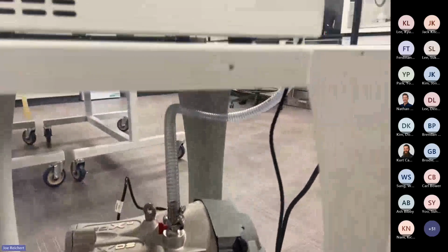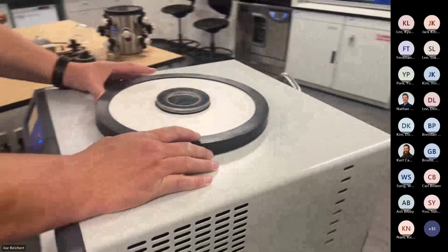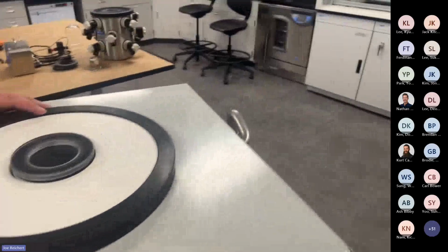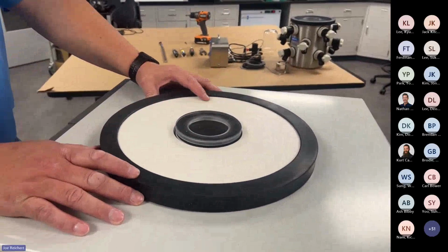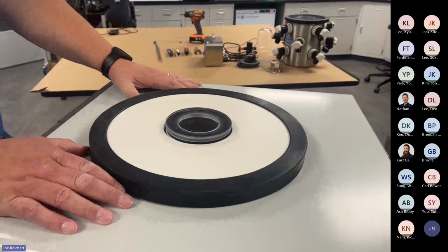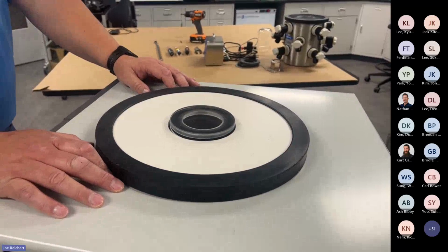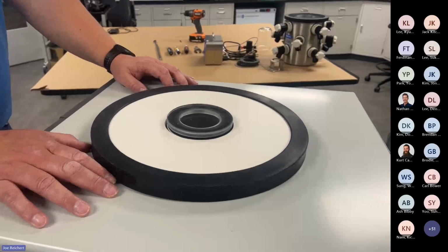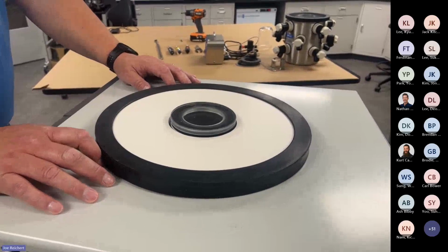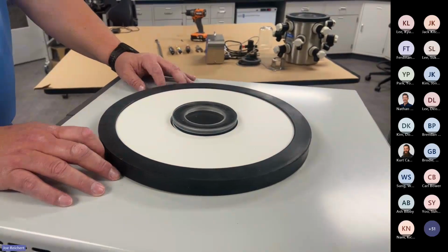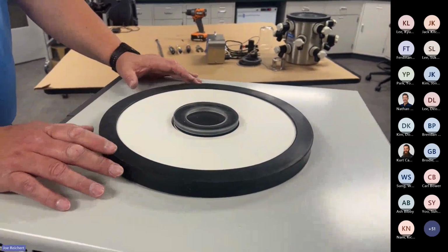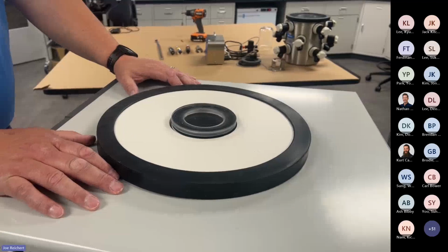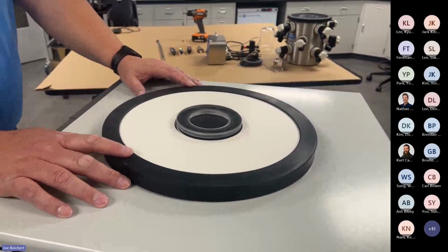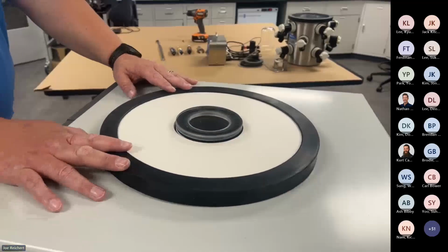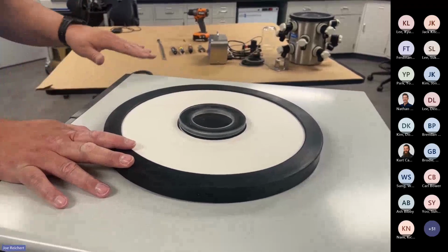The vacuum pumps do need to be purged and maintained, even though there's no oil in them. But you should always purge a pump for about 20 minutes after every drying run. And that just takes opening the gas ballast on the side of it and leaving it open for a minimum of 20 minutes. It helps with clearing out any vapor in the pump, any debris that might have gotten into a pump. On a scroll pump, since there is no oil, there's nothing in there to take any of that vapor or moisture. So you need to clean them out. And the same thing with an oil pump too. Rotary vane pumps need to be purged as well. You'll extend the lifespan of the oil a long ways by doing that.